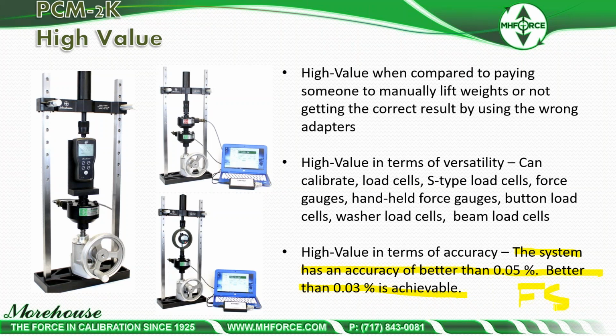So you have a 1,000-pound load cell, you're going to get better than 0.03. You're going to get 0.03 probably at 20%, and you're probably going to get like 0.003 at capacity. So who knows? Numbers on those ranges, you just have to run the data, have to run repeatability, have to run all that stuff. And once you run all that, then you can really know. But when we say this, just know that 0.03 is basically saying that you're going to have two standards, and you're going to switch them out.